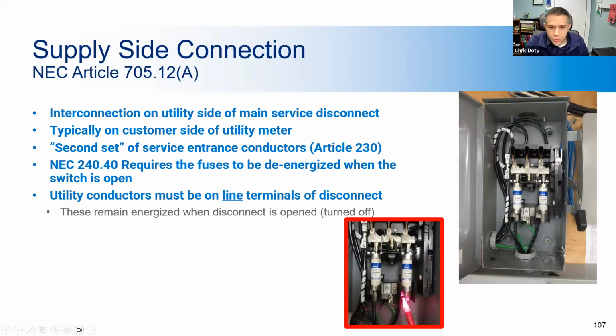All right, so here's a kind of an interesting one. Here we see one of the non-contact voltage testers being used to determine if the disconnect is wired backwards, and it is. So this is an open disconnect, and the bottom of the disconnect is still energized. So what that means is the conductors were installed in the opposite way that they should be, and that means that the fuse is always energized. So you basically don't have a safe way to replace the fuses if you ever need to. The wires that are terminated at the top should have been terminated at the bottom, and vice versa.